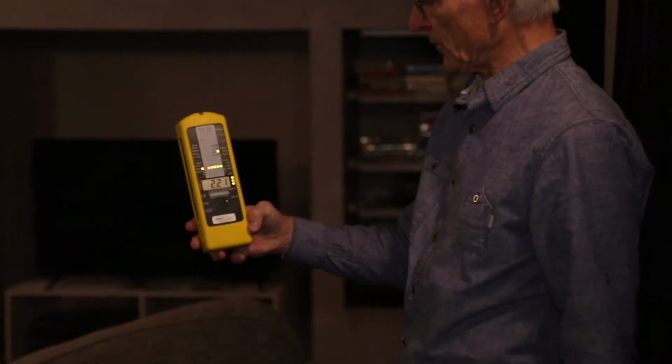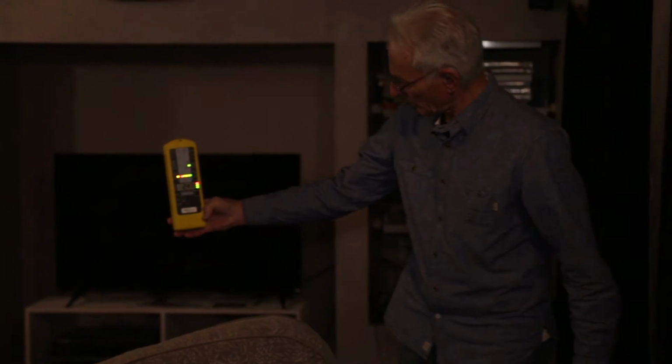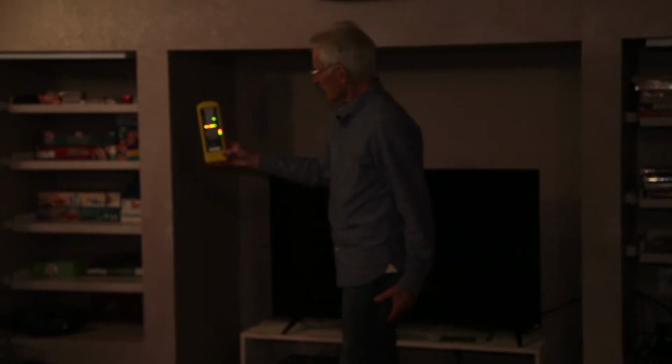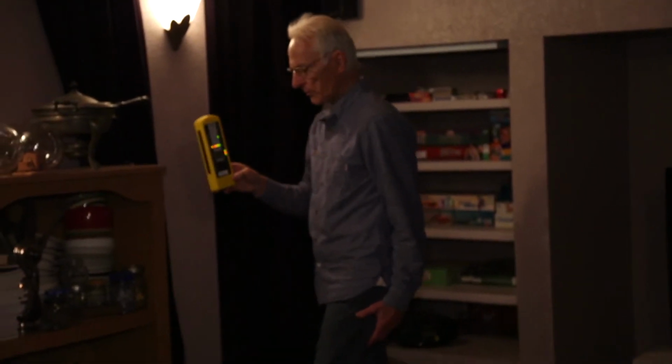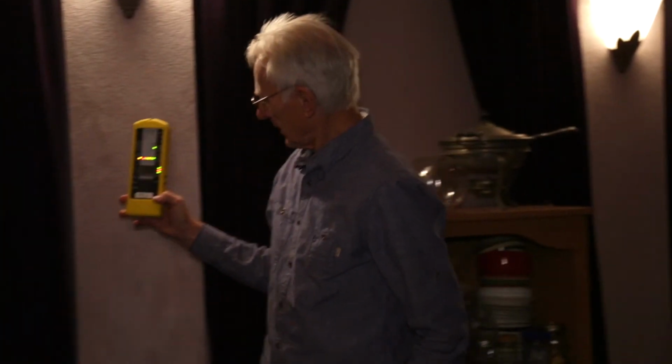So there's one other area that we've identified being affected by that, and that's the home theater, which is directly under the kitchen area. So we'll go take a look at that. So now we've come down to the home theater, and we're already beginning to pick up elevated fields as we enter the home theater. 1.9, nearly 2 milligauss. As we move into the seating area of the home theater, we're at 2.5 milligauss. 2 milligauss at the seat. It's getting less over toward this side of the home theater, which is obviously moving away from the cables that have that net current on them. We move over this way, and it begins to climb again. And if we choose to sit in this chair here, we're basically at 2 milligauss.